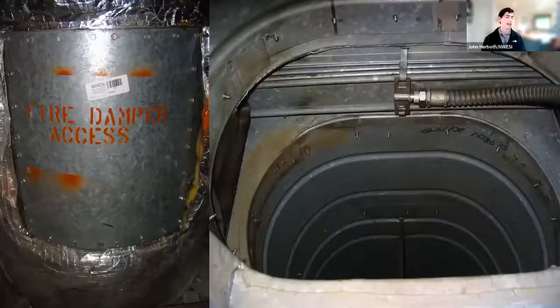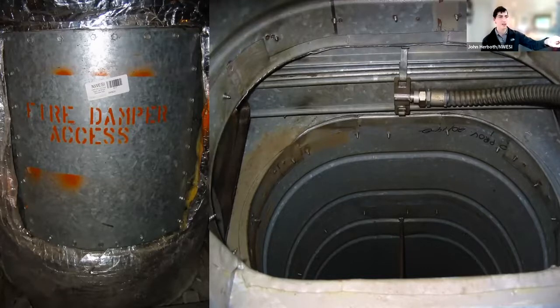And then this is one that Larry thought was hilarious when I showed him this image. This right here is a fusible link, if you can see on the right. This is from a project from my coworker. And I didn't even know what it was. I asked him, and Larry, you asked a few people. We ended up finding the product data for this, and so did my coworker. But that can send electrical, actually a low voltage, to the fusible link, and from the detection from a smoke detector, can send that signal and melt that fusible link. So essentially, it becomes a fire damper that can be closed without a fire.